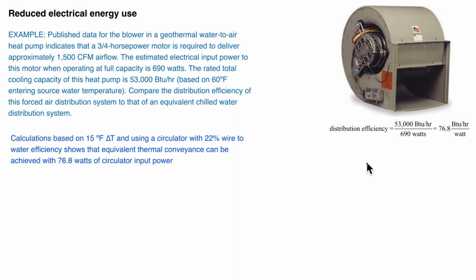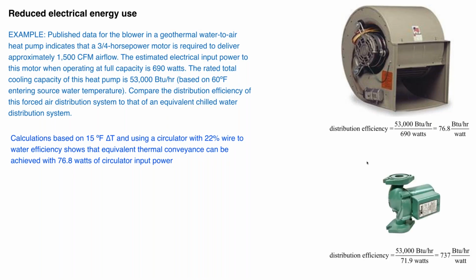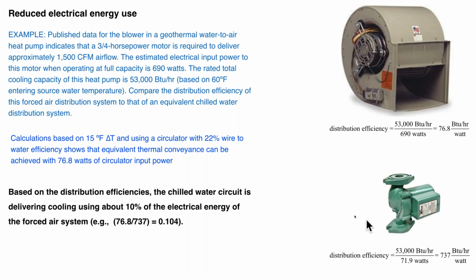Now let's compare that to a hydronic system. Let's say we're using a small circulator like this. It has a relatively low wire-to-water efficiency. It's not a great device as far as converting electricity at very high efficiencies into mechanical energy and imparting that to a fluid. So a typical PSC motor has about 22% wire-to-water efficiency. We could move that amount of cooling with about 72 watts of circulator input power. And I think there's a misprint there. Actually, here's the distribution efficiency over here: 53,000 divided by 72, about 737 BTUs per hour being delivered per watt.